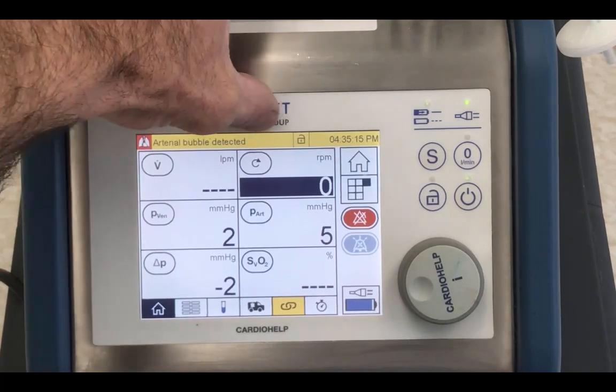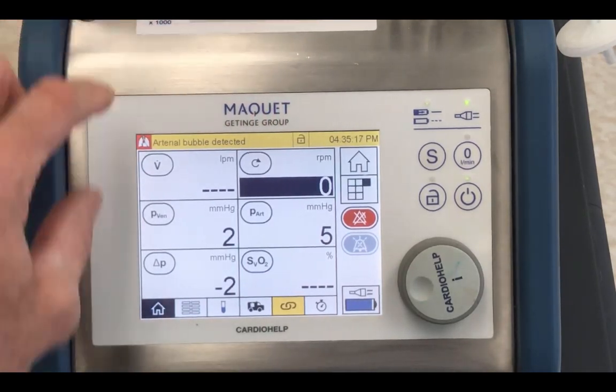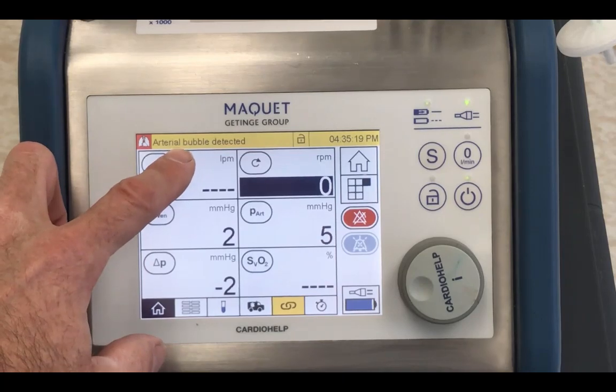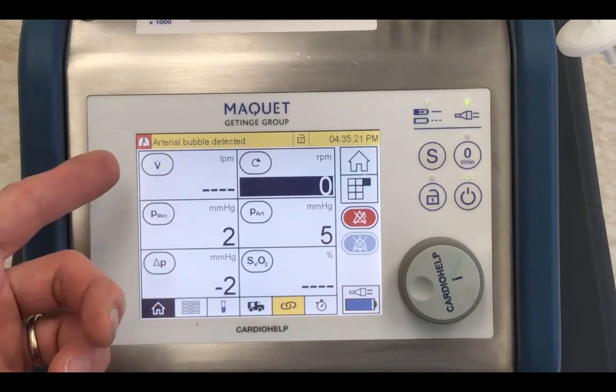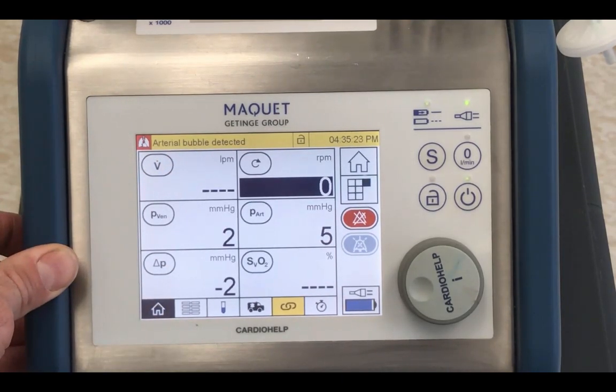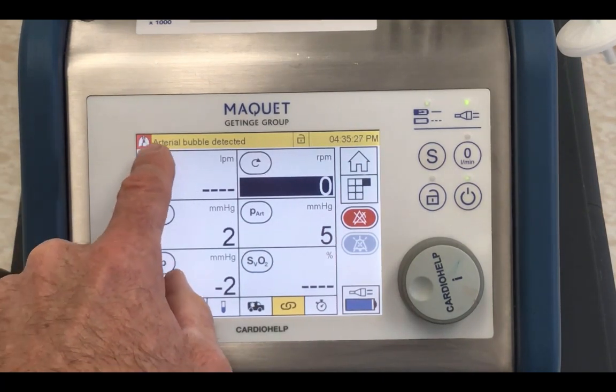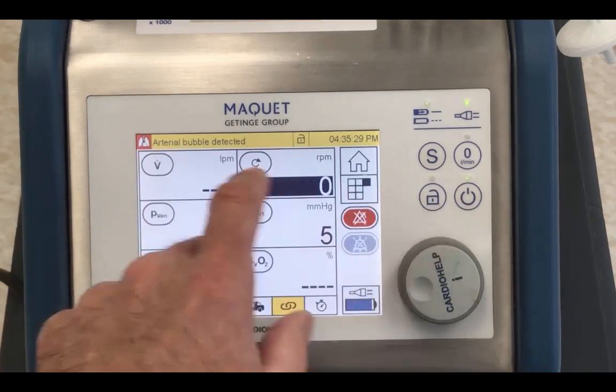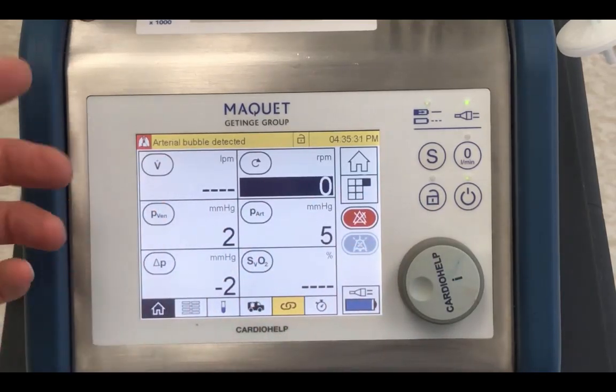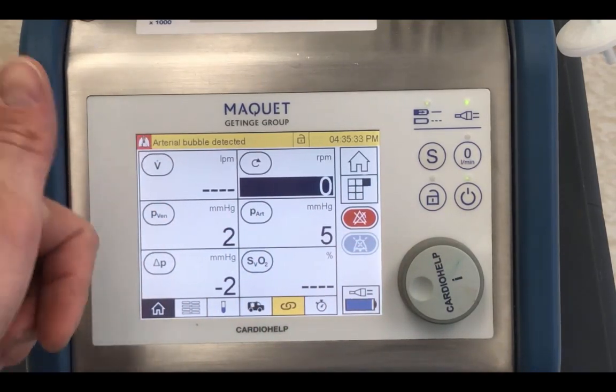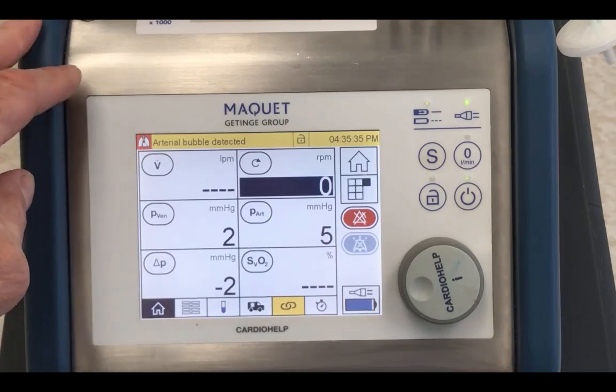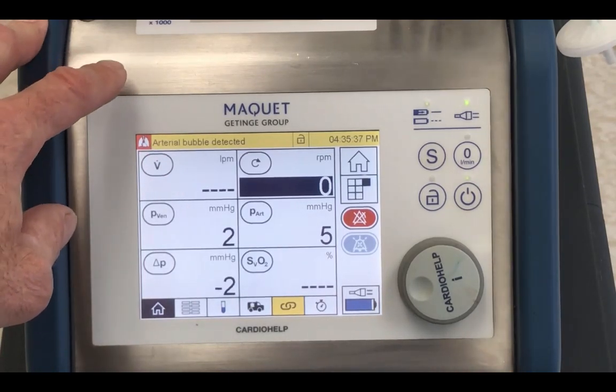This menu here, from there to there, is going to show you the highest priority alarm. At the moment, the highest priority alarm is the bubble, that an arterial bubble has been detected. This can have no color in it. It can be yellow or it can be red, and the words there are, again, highest priority alarm, and not necessarily the most recent alarm, but the one the machine thinks you should be dealing with first.